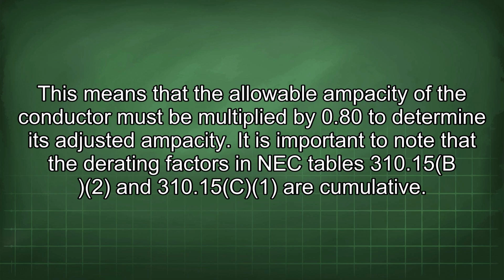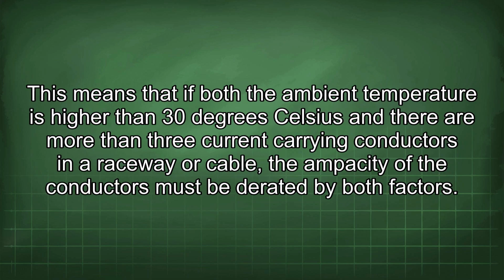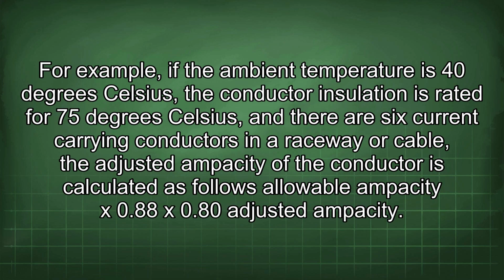It is important to note that the derating factors in NEC Tables 310.15(B)(2) and 310.15(C)(1) are cumulative. This means that if both the ambient temperature is higher than 30 degrees Celsius and there are more than 3 current-carrying conductors in a raceway or cable, the ampacity of the conductors must be derated by both factors. For example, if the ambient temperature is 40 degrees Celsius, the conductor insulation is rated for 75 degrees Celsius, and there are 6 current-carrying conductors in a raceway or cable, the adjusted ampacity of the conductor is calculated as follows: allowable ampacity x 0.88 x 0.80 = adjusted ampacity.